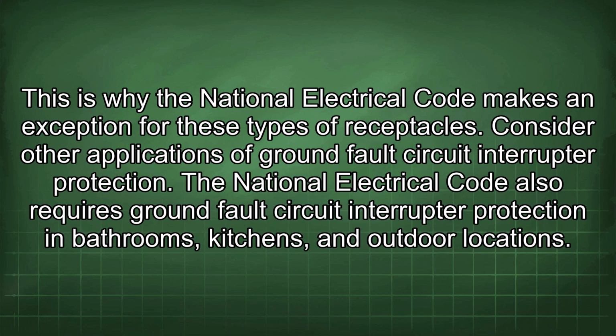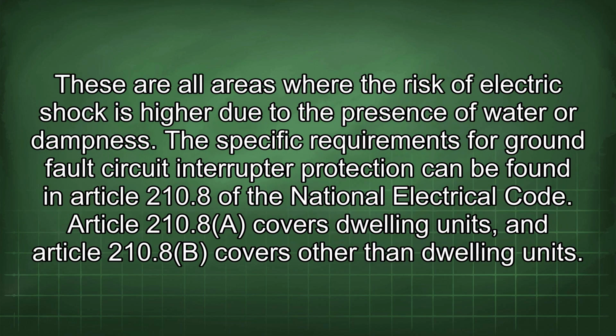Consider other applications of ground fault circuit interrupter protection. The National Electrical Code also requires ground fault circuit interrupter protection in bathrooms, kitchens, and outdoor locations. These are all areas where the risk of electric shock is high due to the presence of water or dampness. The specific requirements can be found in Article 210.8 of the National Electrical Code. Article 210.8(A) covers dwelling units, and Article 210.8(B) covers other than dwelling units.